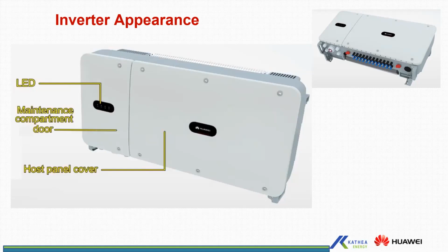And then the other icon is for communication and alarm. Communication, DC, AC, they are all green. If the LED indication is gray, like off, it means whatever it's depicting is not available at that moment. If you lose your DC or your AC, it will simply switch off. And then there is a red icon, which is the fourth icon, which is the alarm. Whenever it illuminates red, it means the inverter is at fault. If it flashes yellow or orange, then it means there is a warning on the inverter.